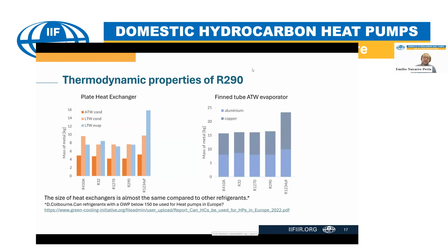From this study, we can see that the size or weight of heat exchangers using propane is more or less similar to that of a heat exchanger designed for R410A or R32, so no increase in cost is expected when switching from current refrigerants to propane. If we compare these results with R1234YF or R454C, however, we see that for those two refrigerants the weight of the heat exchanger has to increase significantly.